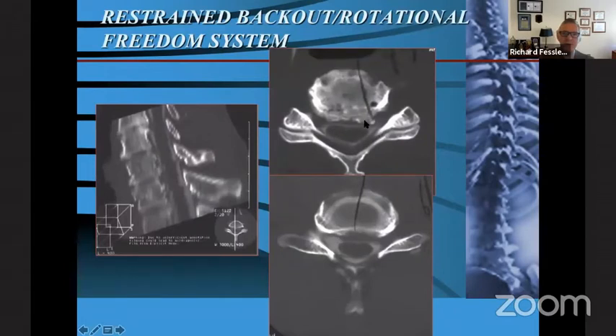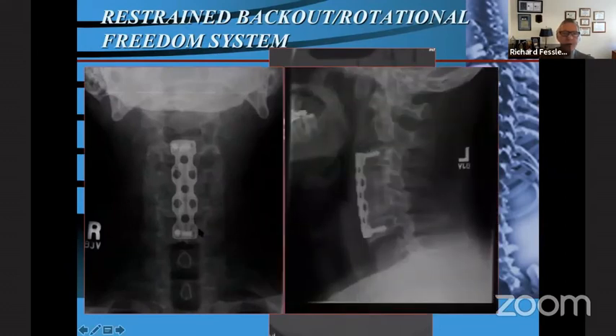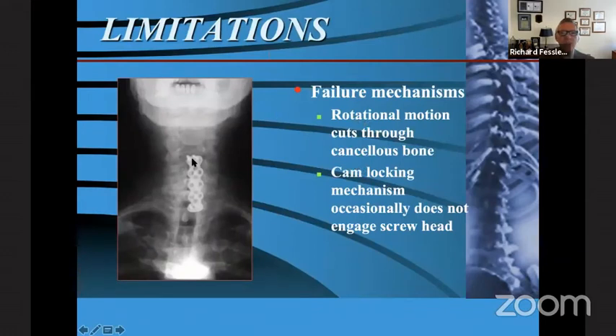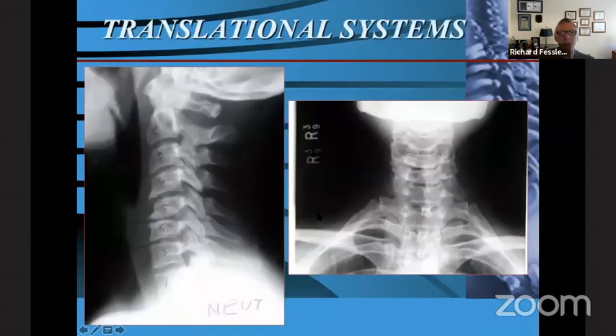Another patient with stenosis and osteophytes extending into the foramen. This was another Medtronic plate where the bottom was a dedicated angle and the top was variable angle — allowing the screw to rotate within the vertebral body. The failure mechanism there was that rotation would cut through the cancellous bone and loosen the plate. There was also a cam locking mechanism that occasionally would not engage the screw head, making it difficult to lock the screw head to the plate.